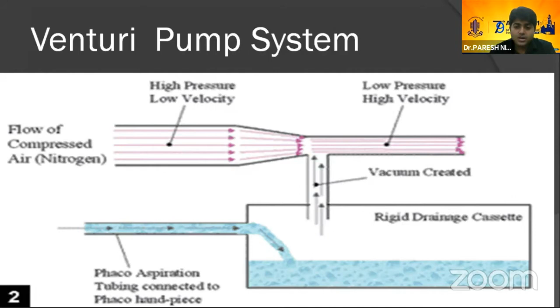The basic difference is that the peristaltic pump is a flow based and the Venturi pump is a vacuum based system. Vacuum is created only after the occlusion in the peristaltic system, while in Venturi, vacuum is created instantly via the pump. Flow is constant until occlusion in the peristaltic pump, whereas in Venturi, the flow varies with the vacuum level. Drainage of the BSS is in a soft bag in peristaltic, and the drainage in the Venturi is in the rigid cassette.